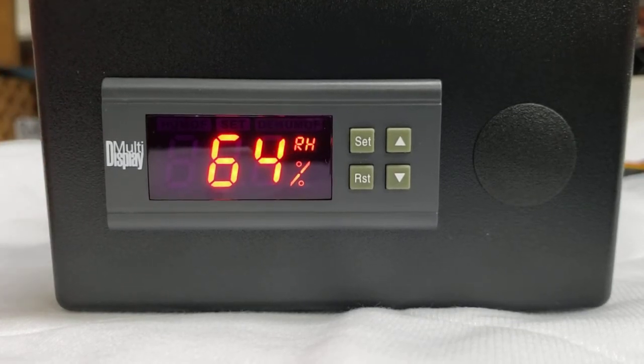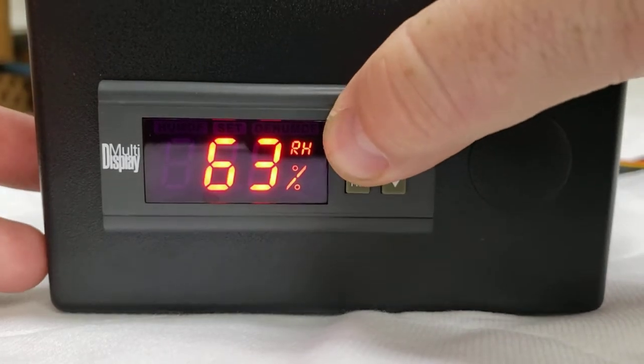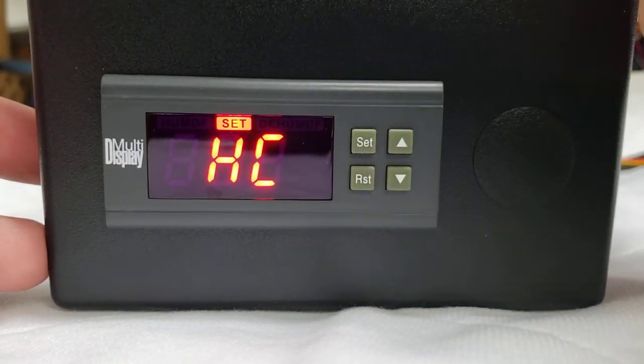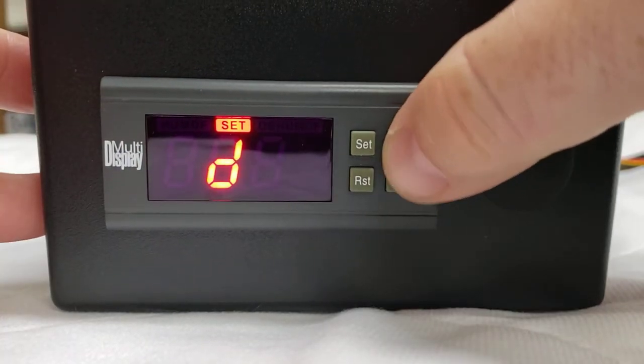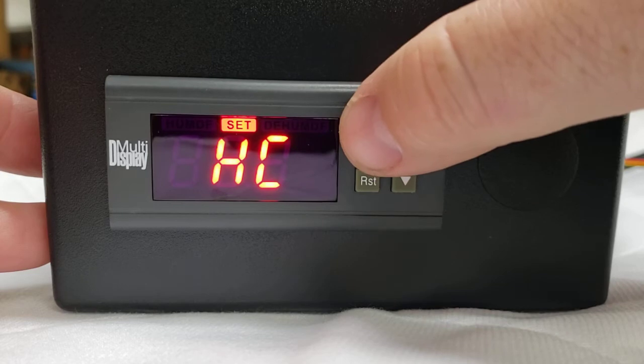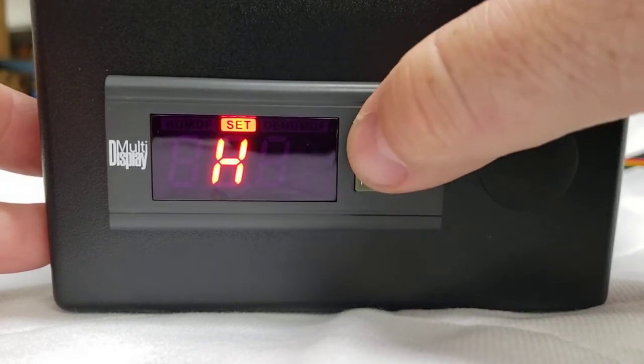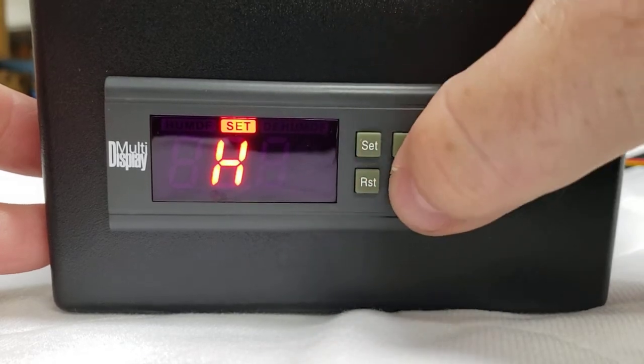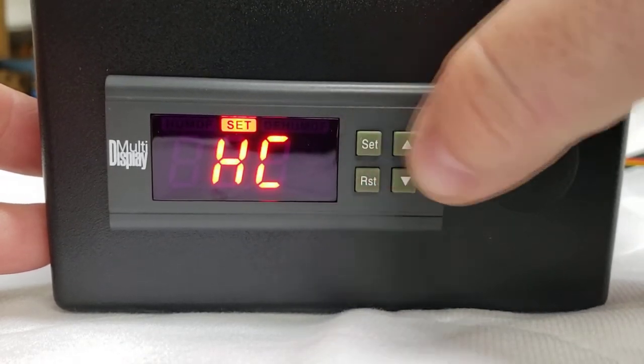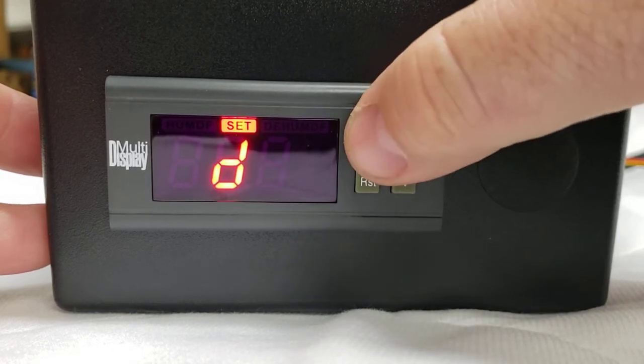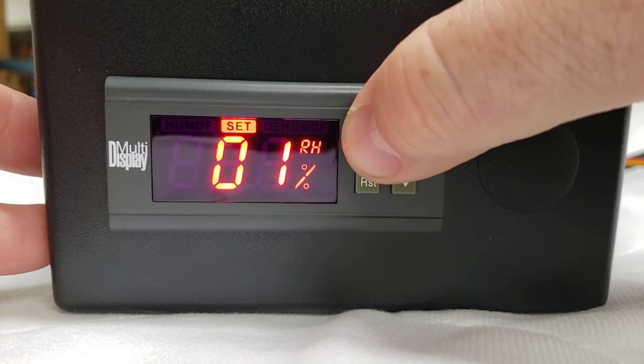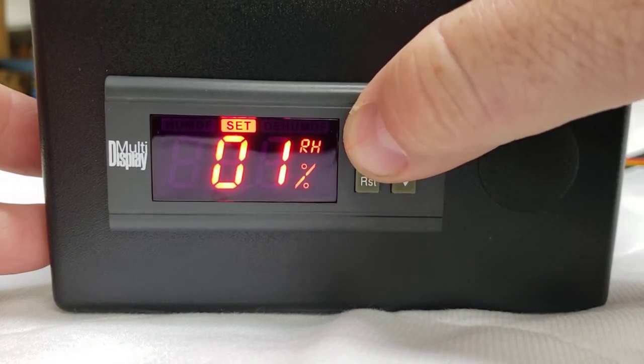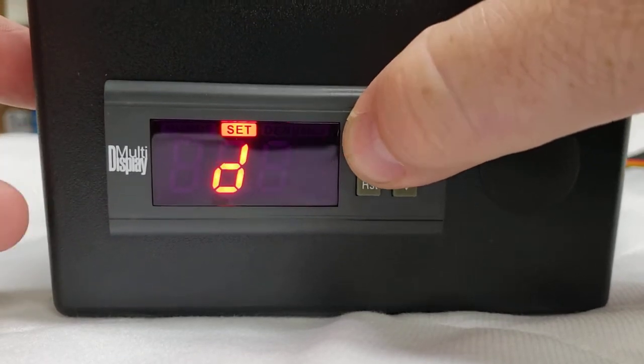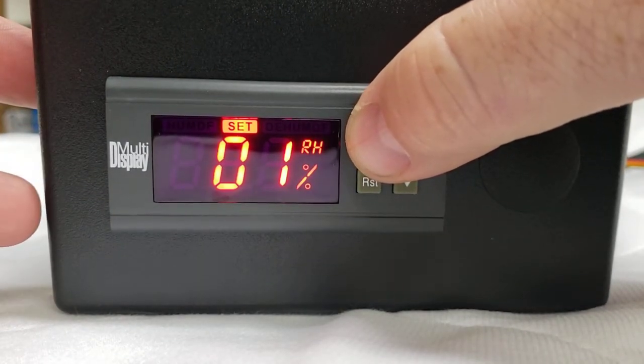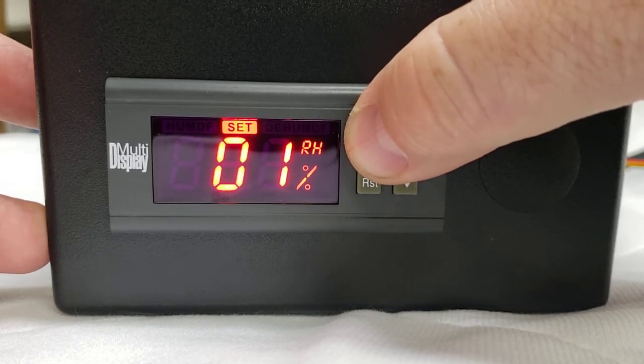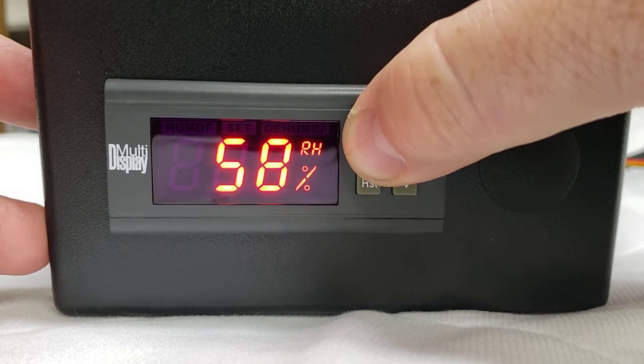To get into the internal settings of the humidity controller, you're going to hold that set button for 3 seconds. You're going to see HC come up, and the HC is to humidify or dehumidify. H is humidify, which is what it should be set for, and C is dehumidify. So the up or down arrow would set those. We're going to set this for H. It'll go back to the HC. Then we hit our up button, which gets us to the D. That D setting is the percentage over or under that you're asking the pump to kick on. We want it to kick on as close as possible and try to hold within 1% of our setting, to minimize that fluctuation. So we set that for 0, 1.